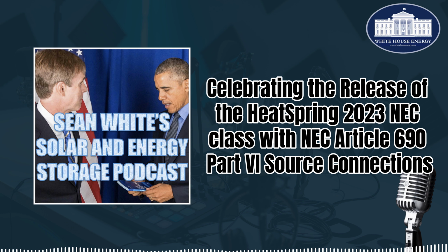And so that pretty much wraps it up for Article 690. The next thing that comes after 690 is Article 691, which is called Large-Scale Photovoltaic PV Electric Supply Stations. And that's really cool. And it means that we don't have to follow all of the stuff in Article 690 if we have a real big PV system that's at least 5 megawatts on the AC side. It's not supplying loads. It's not on a building. We don't have to do stuff like DC arc fault protection. What a nuisance. But it's safe because it's behind a fence.